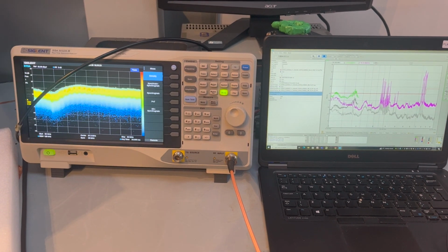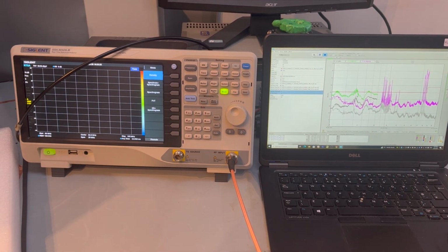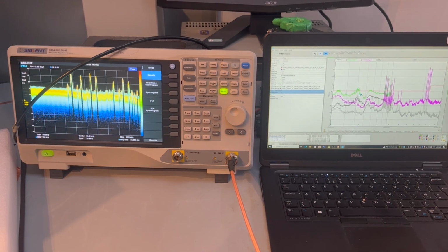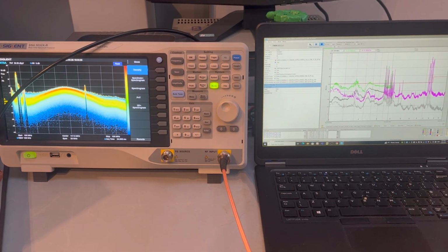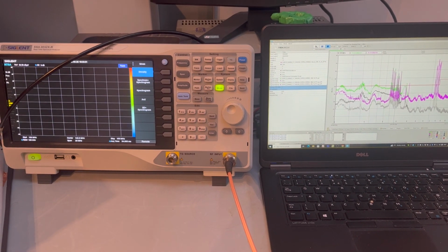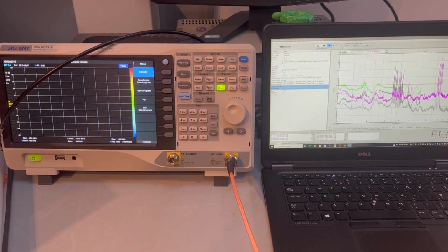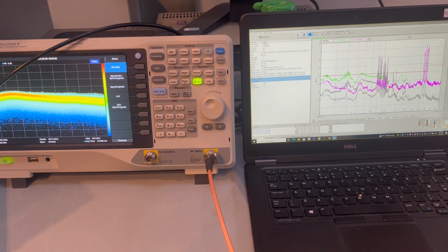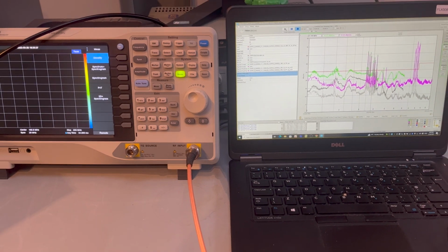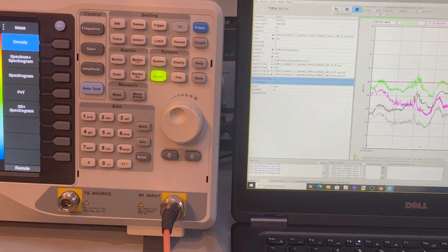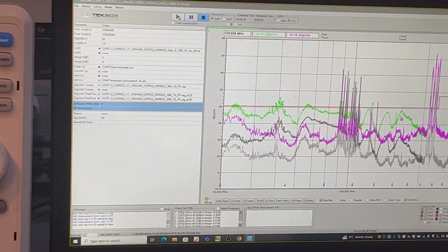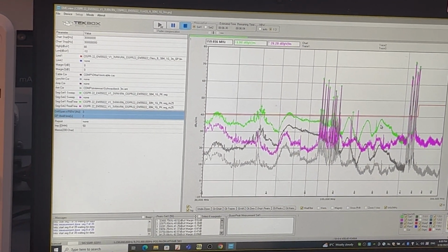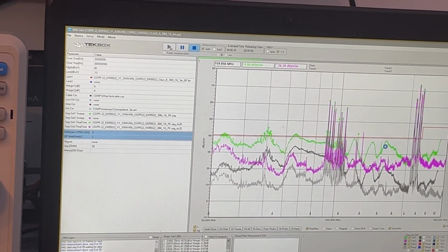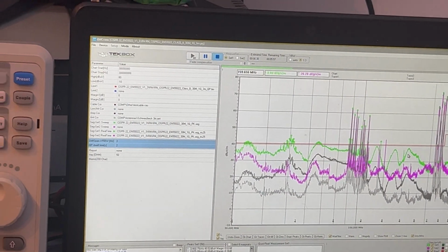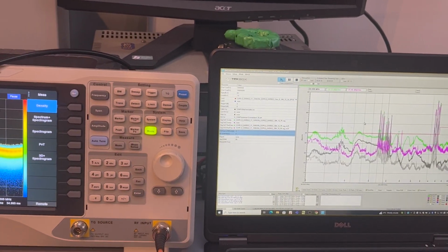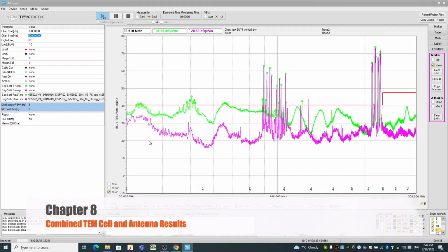As you can see, the green trace is our scanning with the unit on, and if we want to test CISPR22 class B, then we might have some problems here, here, and here. As you can see, it all exceeds the limit. So let's wait until the scan is complete. And as I said, we're probably going to perform a horizontal test as well at different heights. Okay, let's have a look at the results.